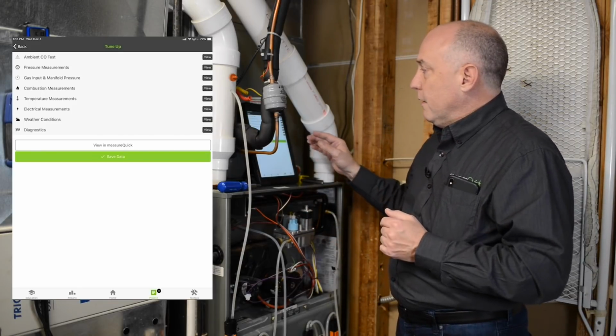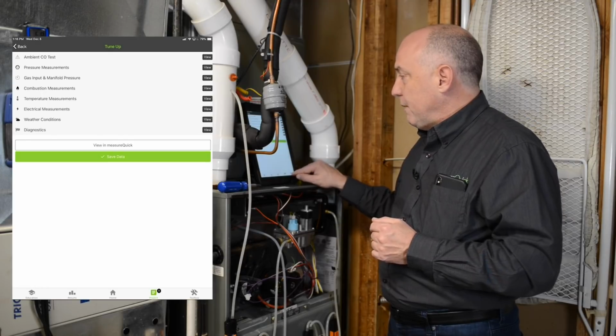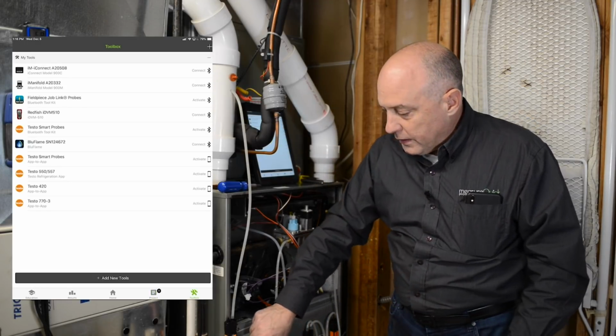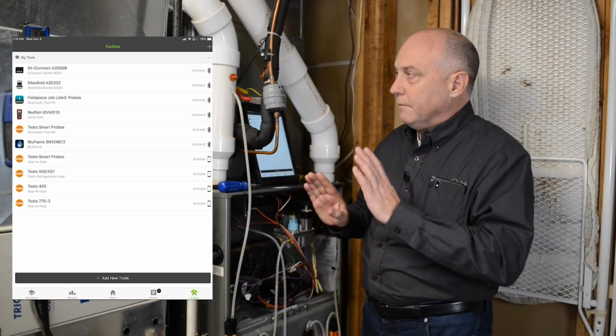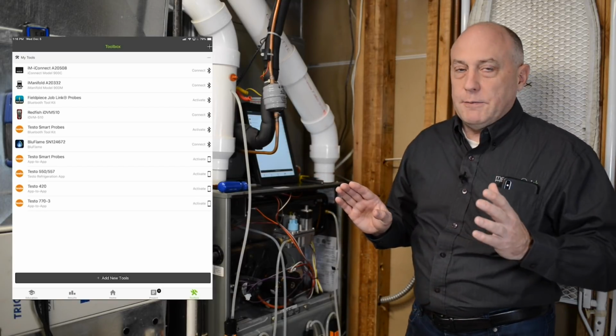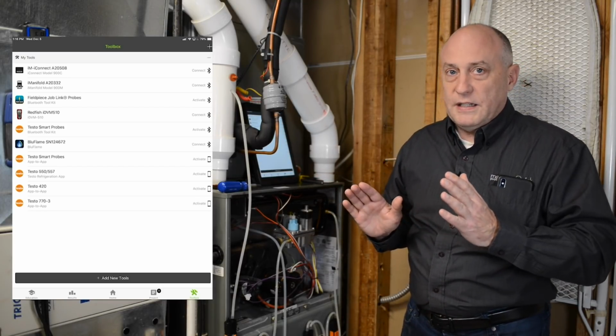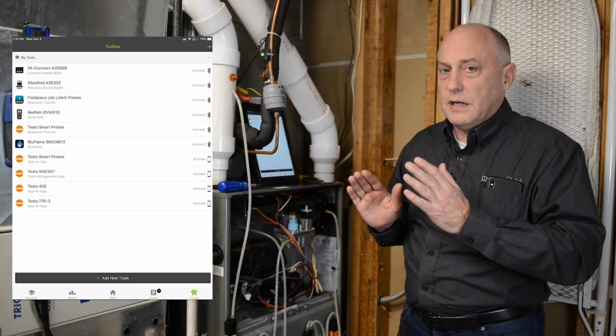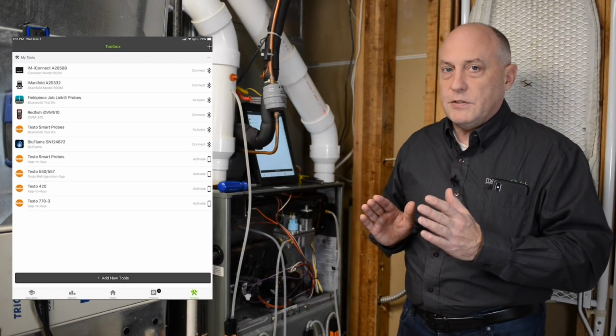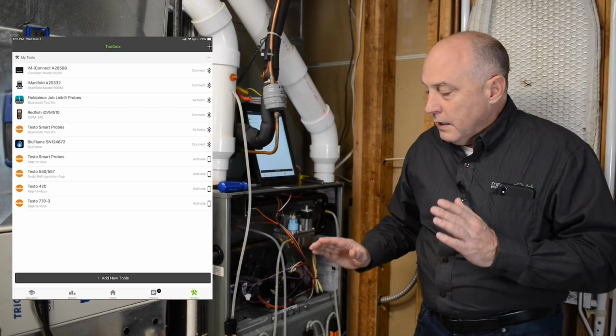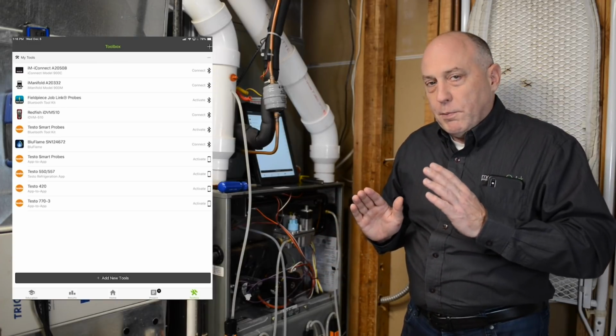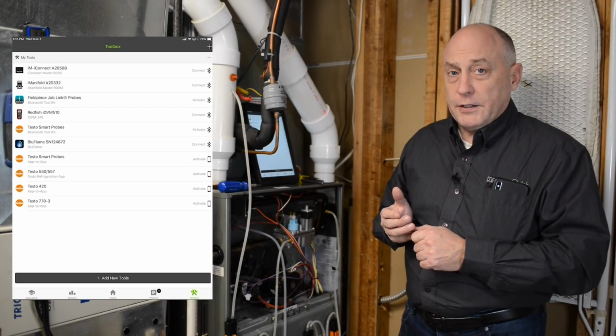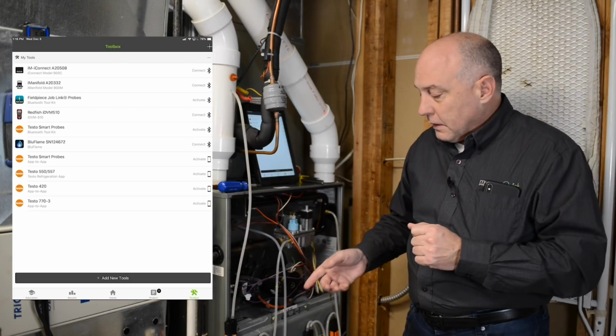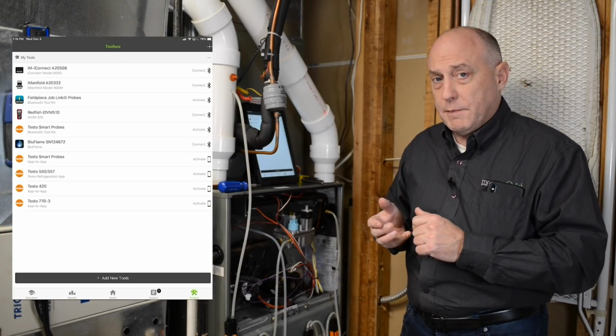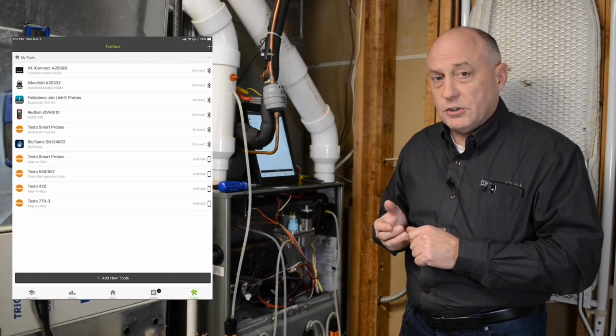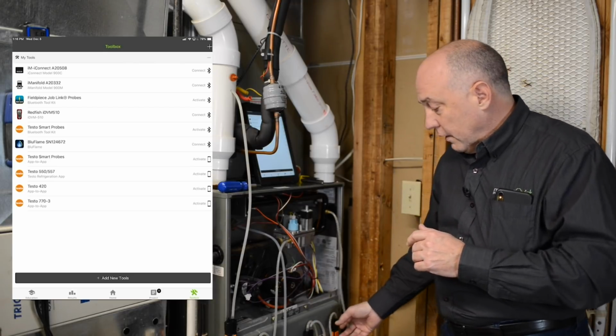So at this point, what I'm going to do now is simply go into my toolbox and turn on all these different manometers here. Now, this may look a little bit crazy to you, but if you're like me and you want to get things done quickly, this is a small investment in tools that'll save you a ton of time. On a gas furnace, you have multiple pressure measurements you have to take. You should be monitoring your stack pressure or vent pressure, your incoming gas pressure, your manifold pressure, and your total external static pressure, just four of them here.